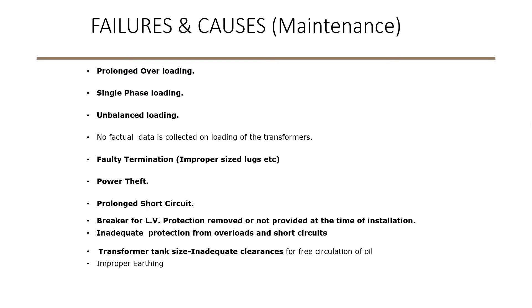Transformer tank size is reducing day by day, causing inadequate oil circulation and overheating—that's a relevant criterion, as we are optimizing size without knowing the engineering facts. Improper earthing is also very important. Earthing in the distribution sector is a topic that could be covered separately, and a lot of transformers fail just because of improper earthing.